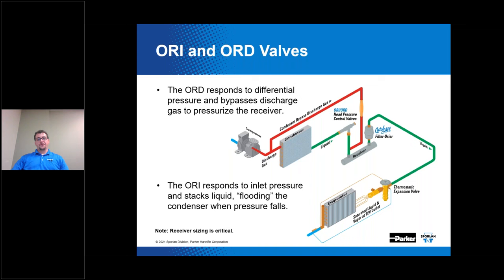The ORI responds to the pressure at the outlet of the condenser and is fully open when the condenser pressure is above the ORI set point, such as during high ambient. As your condenser pressure falls below the valve setting during low ambient conditions, it modulates — backing refrigerant up into the condenser, flooding that condenser coil, and lowering the capacity of the condenser. Its function is to maintain a constant pressure in the condenser. By flooding the condenser, we're reducing the condenser's capacity by taking away its effective surface area. The continuous modulating of the ORI influences receiver pressure, but it's only directly controlling condenser pressure.